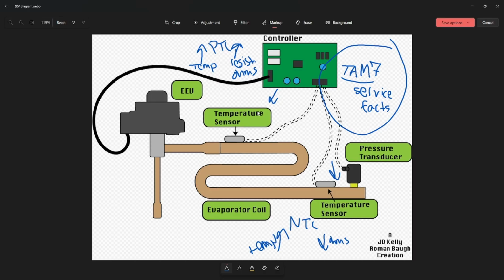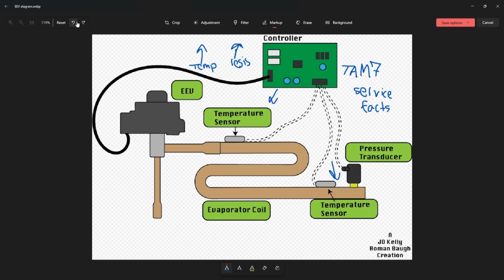So the temperature sensors are what fail most often on these guys. So the majority of the time, if you're having an issue where you're suspecting the valve is not doing its job, you'll want to start with the temperature sensors. Start by checking the resistance on them. Start by ohming them out, seeing what you're getting based on the temperature that you've got of the lines. Or if you unclip them from the lines, just let them hang in the return air. See where your resistance is. There's a variance that's acceptable. It's usually plus or minus 3 degrees. That's acceptable. Anything outside of that plus or minus 3 degree range is considered failed.